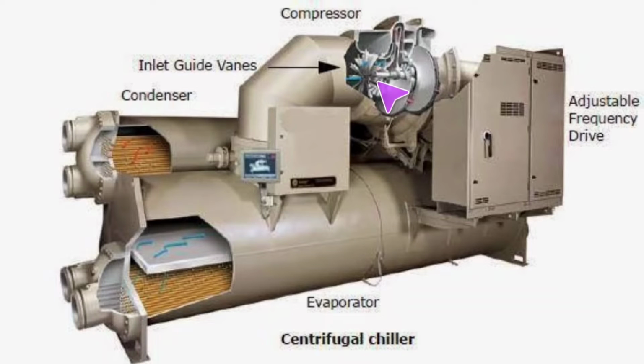Trane is a lot less tight on their tolerances compared to somebody like York. York tells you that if you can fold a dollar bill 4 times and then make it fit between the vanes when they're closed, and York's vanes actually overlap each other. They have to be machined in. The York chillers aren't going to do well. They're going to give you trouble, specifically like their YK and YT series. Trane is a lot more loose with that. They're not near as restrictive, and their vanes don't actually overlap. They kind of just butt up to each other. So much different design, much different setup in that way. But still, nonetheless, that's going to be a critical component to this entire machine and its calibration. And this is controlled by a little armature right here.